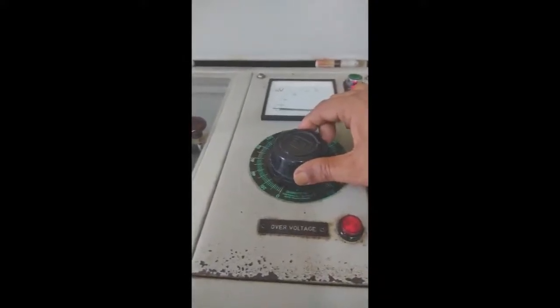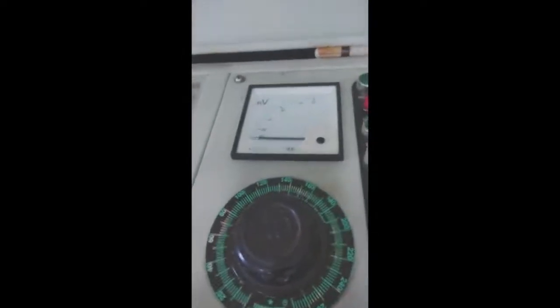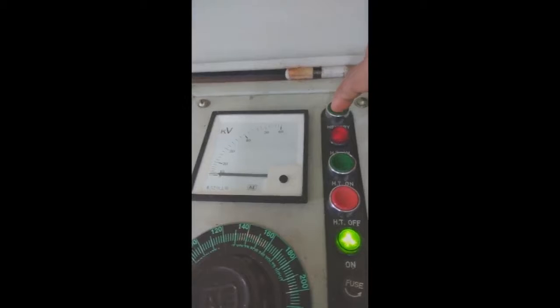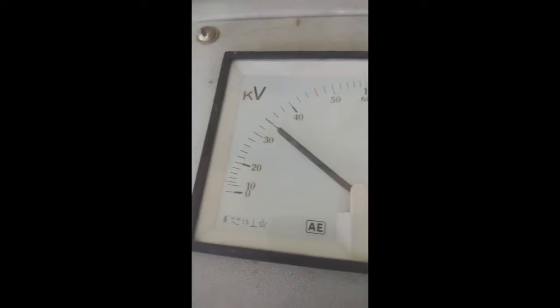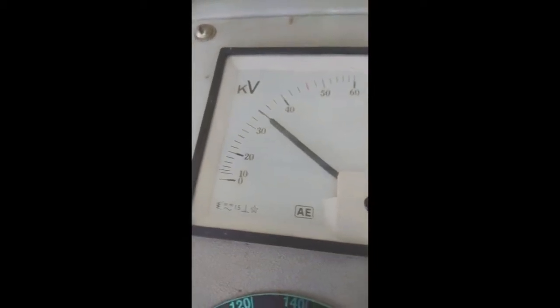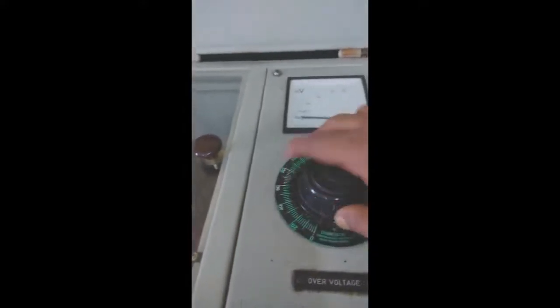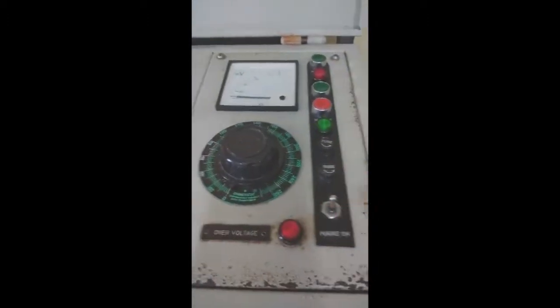Now we will gradually increase the applied voltage of those two electrodes, and it will just trip, and then by pressing this memory we can get the actual breakdown voltage, that is 34 kV. That is 34 kV. Then we will write this data in our data sheet, and just turn off this variac and the main switch.